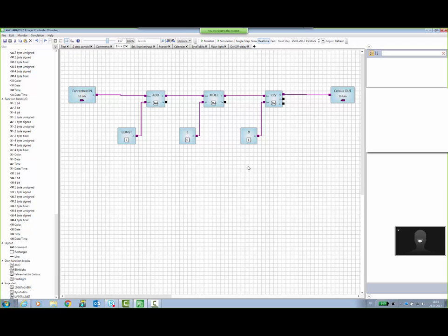So how to do this practically? As mentioned by Jürgen, first of all you create the standard function with KNX inputs and outputs. You test everything with simulation. And then you copy only your logic, which is not the inputs and outputs, but only what's between them. So I mark this with the left mouse button, and then I have the option to copy and, of course, to paste as well. So I duplicate only my logic, same as before, but with no inputs and outputs connected.